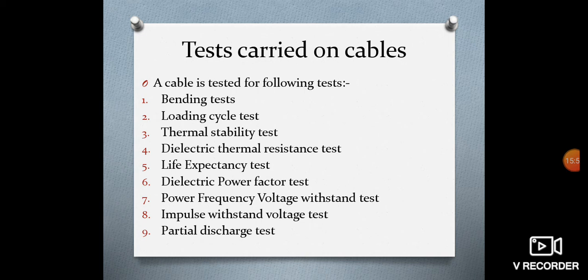Partial discharge test. Partial discharge measurement of cable is very important as it gives an indication of the expected life of the cable, and it gives the location of the fault, if any, in the cable. When the cable is subjected to high voltage and if there is a void in the cable, the void breaks down and the discharge takes place.